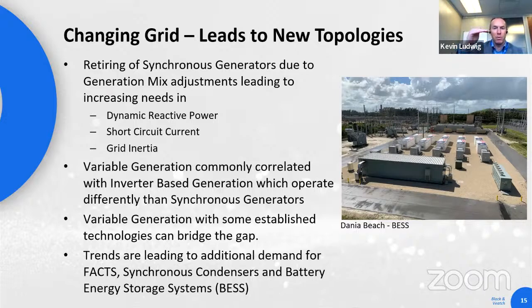Where I'm going is when I said there's two elements: one is the guarantee of performance at the point of interconnect. Now, transmission planners understand the inherent limitations of the renewable generation, and so there is transmission planning functions that happen as all of these devices are looking to interconnect into the grid. As these devices become more prevalent and transmission constraints are identified, which would result in reliability issues, the transmission system planners then identify additional elements which must be added into the grid to allow the reliability to be maintained. So those functions may exist outside of the plant itself, and it may be a situation where the cumulative effect of many renewable plants results in the addition of a FACTS device or some other supplemental device in the power system.